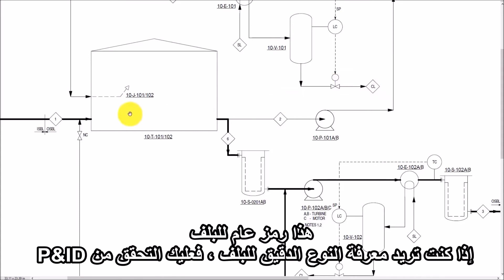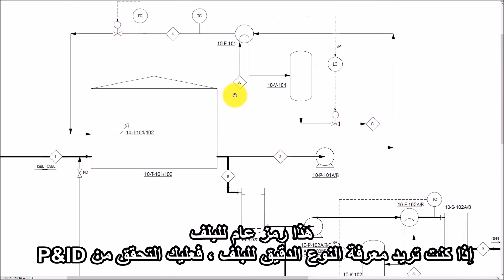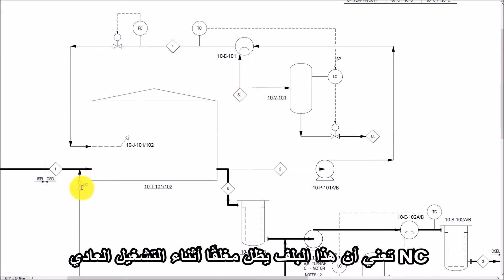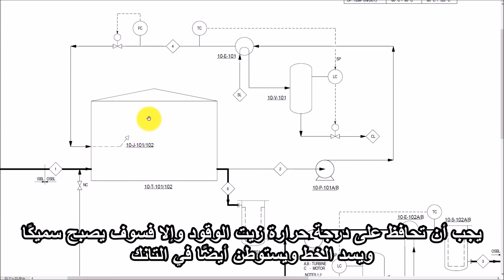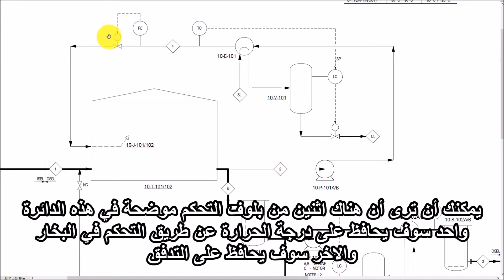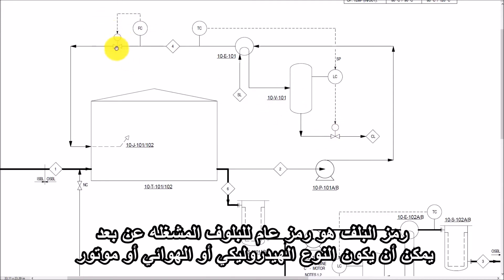This is a generic symbol of a valve. If you want to know the exact type of valve, you have to check the P&ID. The letters NC mean Normally Closed — that means this valve remains closed during normal operation. Now look at this loop. This is a circulation loop. Fuel oil from the tank is supplied to the pump, which is passed through the heat exchanger and returned to the tank. You have to maintain the temperature of the fuel oil; otherwise it will get thick, block the line, and also settle in the tank. You can see that there are two control valves shown in this loop — one will maintain the temperature by controlling the steam and the second will maintain the flow. The symbol of the valve is a generic symbol of a remotely actuated valve.